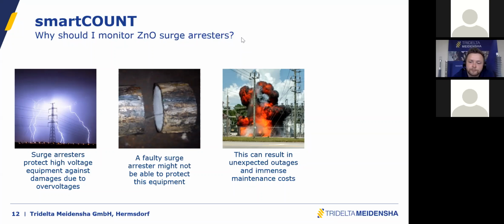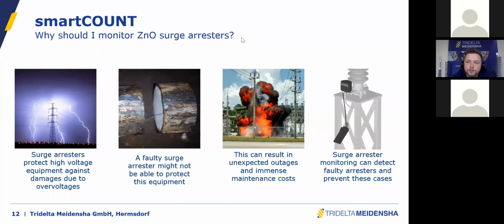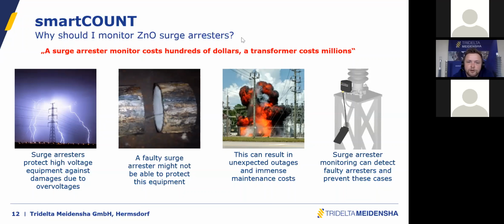How can we prevent this? We need to install a surge arrester monitor on our surge arrester to find this one surge arrester in the whole surge arrester fleet which is or which becomes defective. So you can't say I have a replacement surge arrester, because at the moment the surge arrester breaks down, you are not there, or you don't get it. You will not receive any information about the health of the surge arrester. The aim is to find surge arresters when they get bad and before they fail. And of course, a surge arrester monitor costs, or let's say should cost, only hundreds of dollars, and the transformer is worth some millions. So you have to consider this.